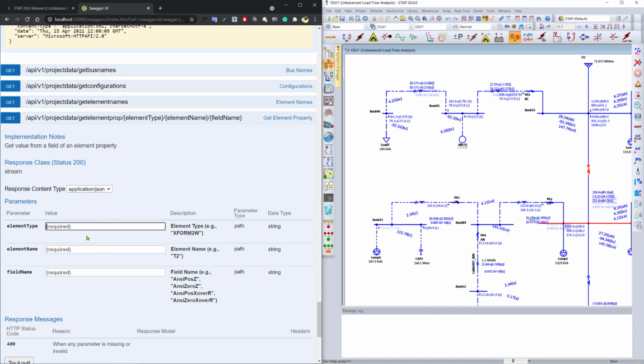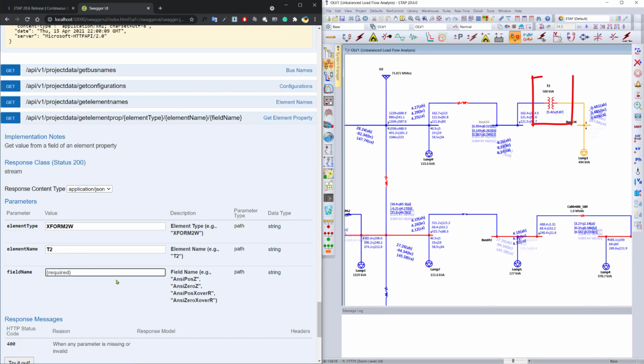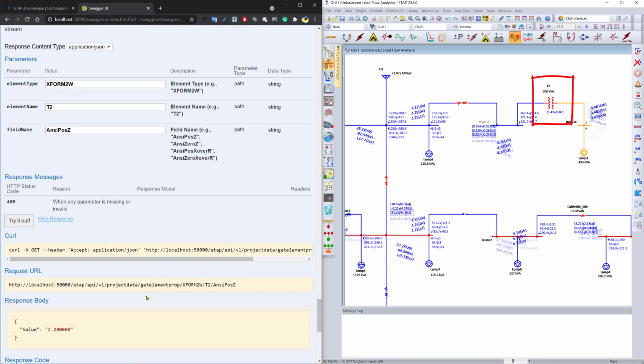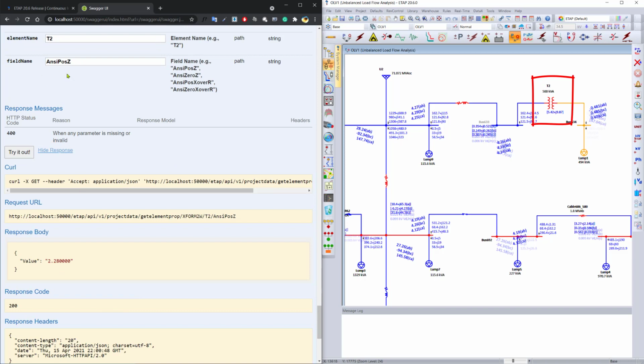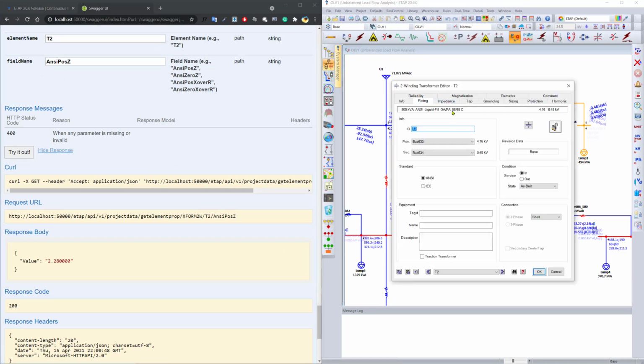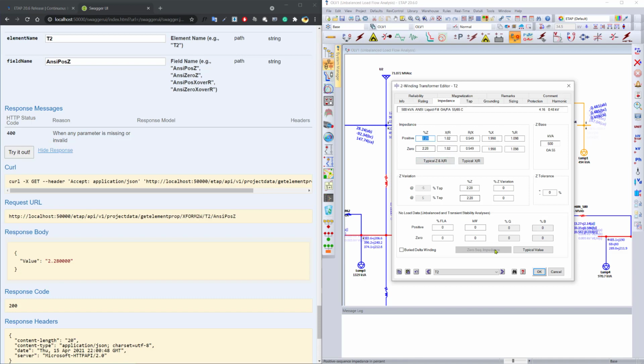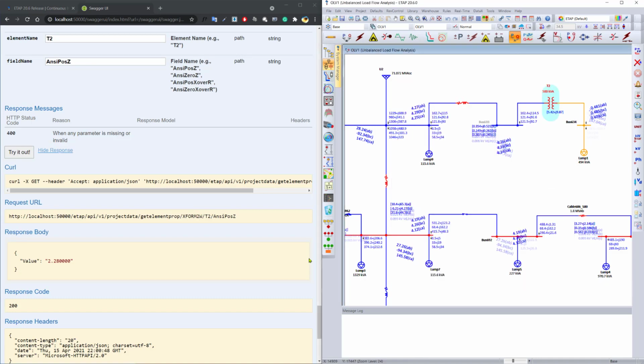If you want to get information about our two-winding transformer, T2, and we want to have access to this particular field, which is the positive sequence impedance of the transformer, we can simply ask the program to query and it returns a value of 2.28, which we can essentially compare and see within the actual application.